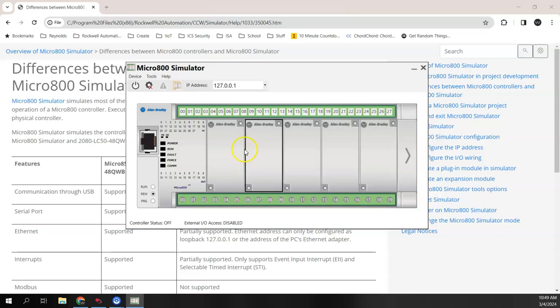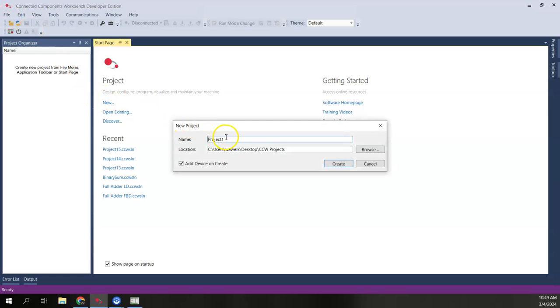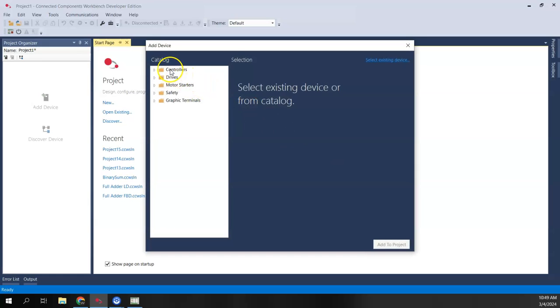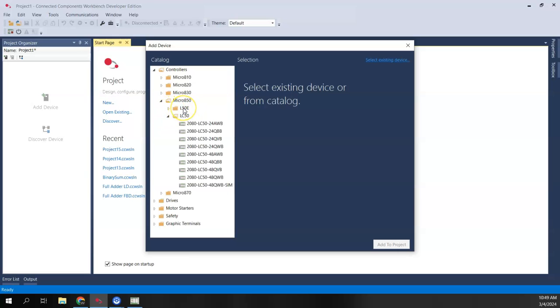Before we configure the simulator, let me first create a project in CCW. We're going to create a project for the simulator: go to New Project, call it Project One, and click Create. Under Add Devices, go to Controllers and then Micro 850. We need to choose the LC50 — the L50E is the newer generation with enhanced Ethernet, but the simulator lives underneath the LC50.